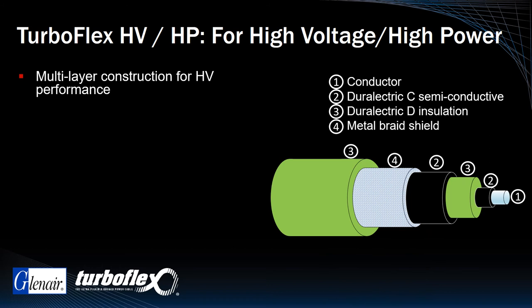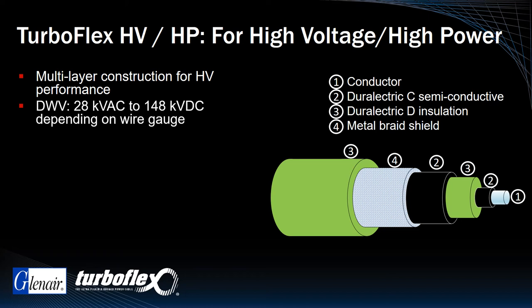As shown in the numbered graphic on the right, this is a multi-layer construction cable with four separate layers of special purpose Duralectric material, including two layers of Duralectric C, a semi-conductive insulator, and an outer jacket made from Duralectric D. TurboFlex HVHP is designed for high DWV applications from 28 kilovolts AC to 148 kilovolts DC, depending on wire gauge.